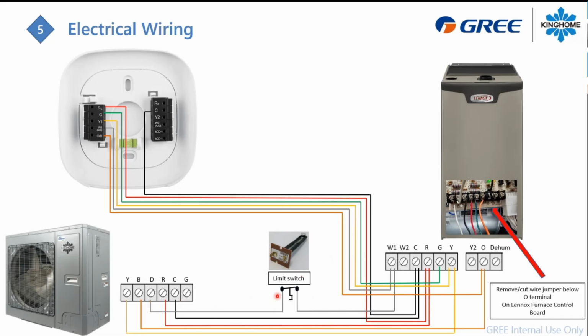So what you can do with the system is, when you have a call for defrost, you will push 24 volts through the limit switch. The limit switch is closed, so you will have this connection going to your W1. So the furnace will start, okay? During the defrost cycle, the furnace can start, and then when you hit 100 degrees Fahrenheit, the limit switch here will open. That will cut off the W1 call, so the furnace will stop. That will provide enough heat in the plenum to not feel that cold draft air, but you will not heat the refrigerant enough to make it boil.